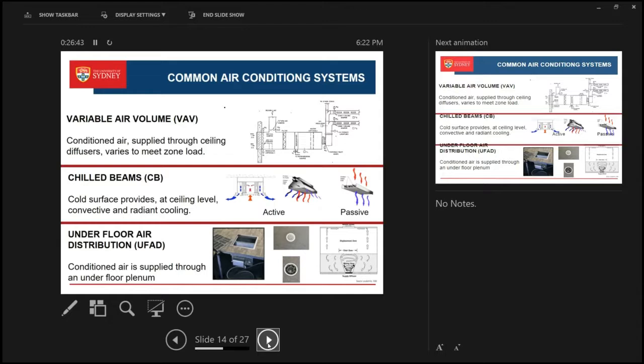There are two types: active and passive. Passive is where you don't have a fan, it just relies on a cold surface—like, say, instead of a projector, you get a cold surface and you get convection, and that's how you get cooling within a zone. Active is where you have fresh air, and the amount of air coming through induces the return air, giving you cooler air coming out of the side. With the passive system, you still need conditioned fresh air, because you need to provide the ventilation flows—7.5 per person in terms of meeting code requirements.